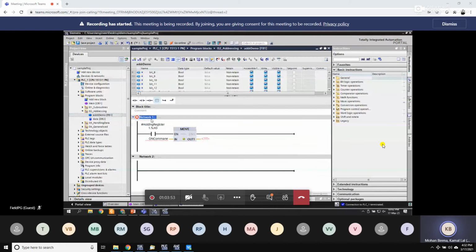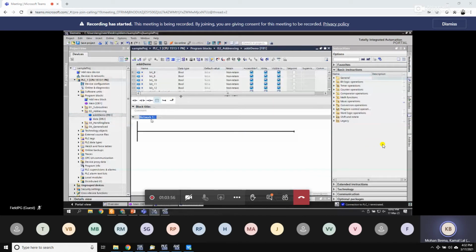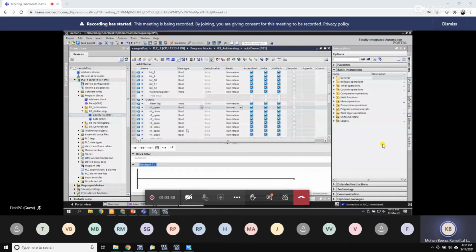So for that, I want to introduce you to the next topic, the concept of the AT keyword or AT overlaying, for the variables we have in the block interface. This has to be set in the IDB for this to work. So if I create the very next variable, var or status, you see this is actually acting as a separate variable with the same type, word, int, bool, whatever is possible.